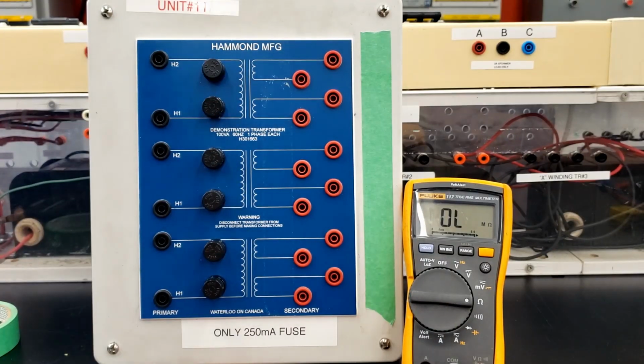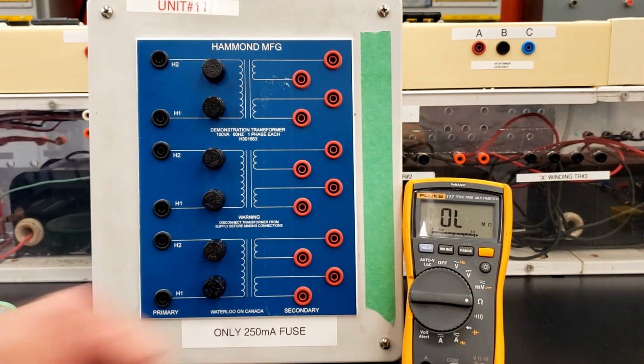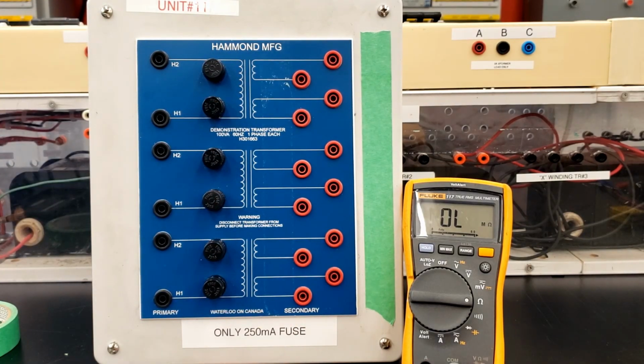We want to do those tests prior to even energizing the transformers. So take the time, check the fuses, check the windings, make sure everything's good, and write down those resistance values.